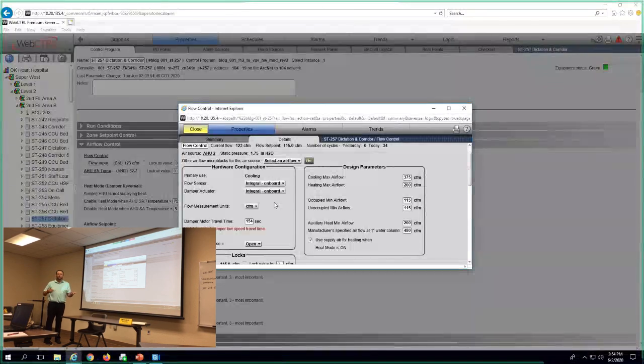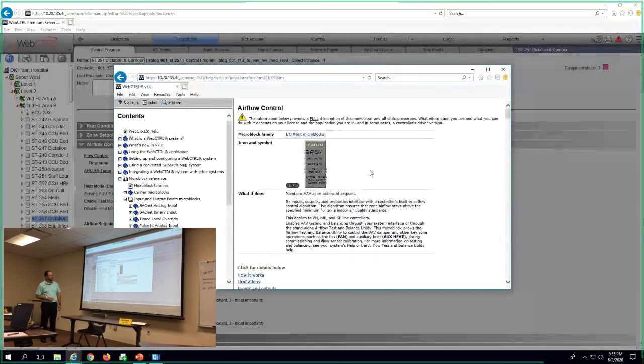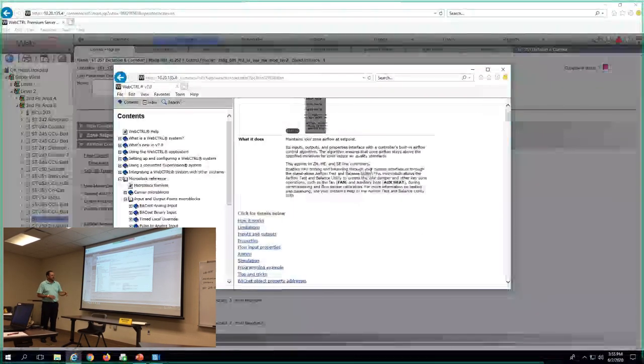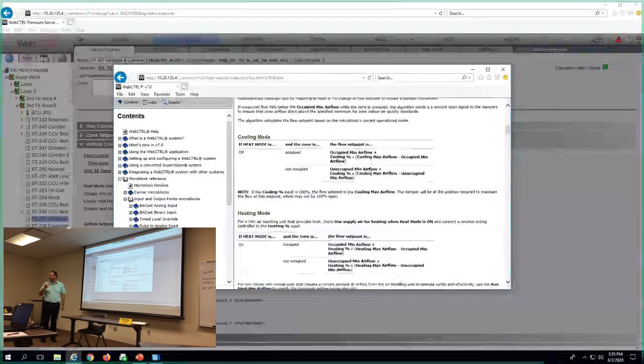Yeah, because we don't have a morning warm-up cycle because you're always occupied. Now, if we had a morning warm-up cycle, generally this would be 375. Same as cooling. We would have the air handling unit start pumping out hot air. We'd warm the space up real quick, but we don't have that part of the sequence. But so it'll be, when you start calling for heating, it'll be at 200 CFM. Does that make sense? And again, click on the help button over there in the top right corner. Hope it doesn't make a liar out of me. Go down and you can click on how it works. It will kind of tell you how it's using those set points.